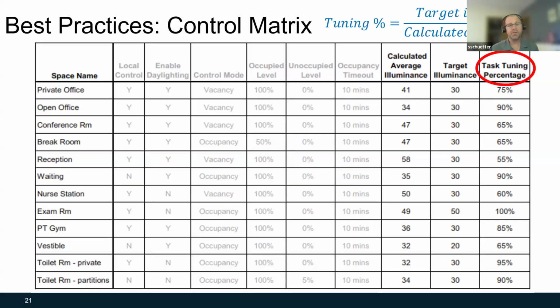A control matrix or schedule such as this, which details the lighting control design intent, can be easily incorporated into design documents, which ensures that the contractor has a clearly defined scope that must be implemented during the construction phase. However, as mentioned previously, care should be taken when implementing task tuning to understand user needs of a given space, so these percentages should be a starting point and adjusted as needed through occupant feedback.